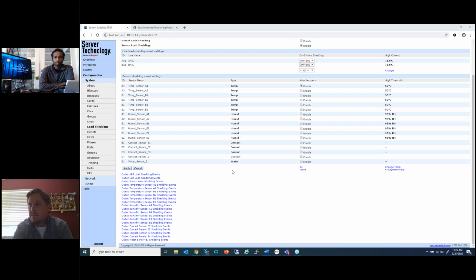The way you would achieve that is you can have more than one temperature sensor. Obviously, we have up to 6 in what I just showed you today. So you can have different thresholds with different sensors that can trigger events to switch things on at different levels of temperature. At one temperature, you could have an outlet switch on and turn one of the fans in the door on, and if temperature continues to rise, you could follow up and have a second outlet switch on additional fans or additional cooling units.